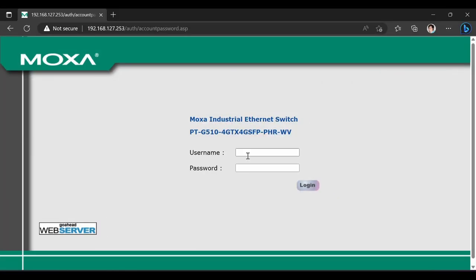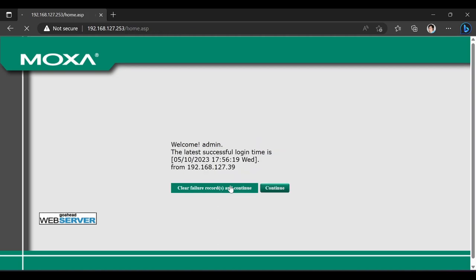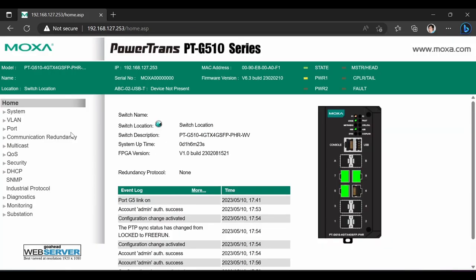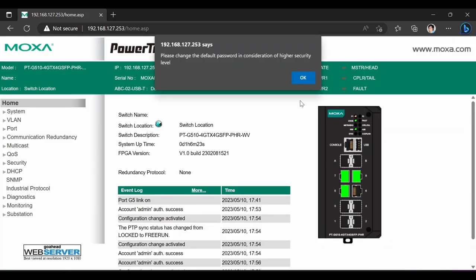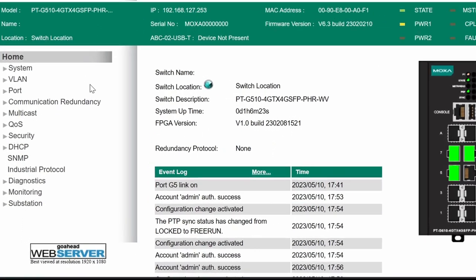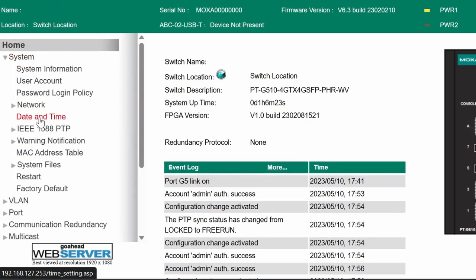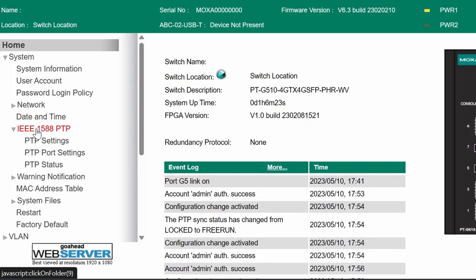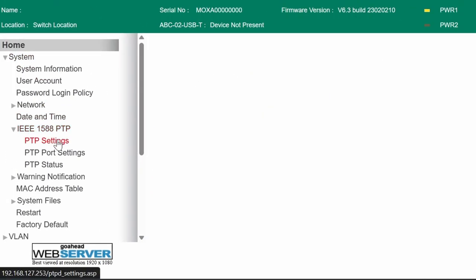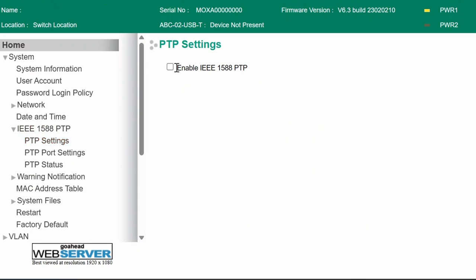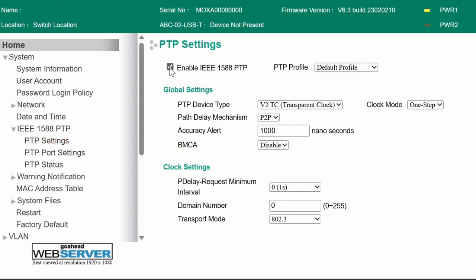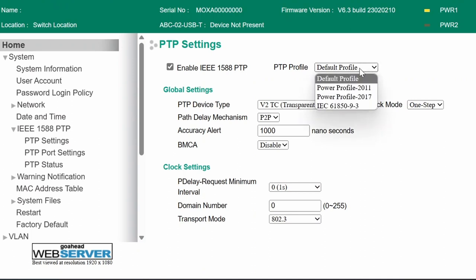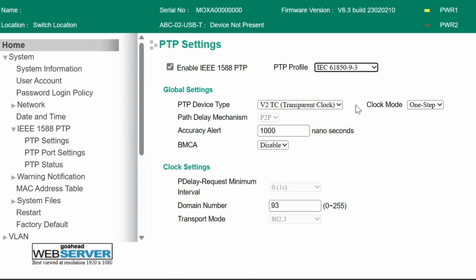Now let's log into the Moxa switch. I'll start with PT-G510 and navigate to system IEEE 1588 PTP PTP settings page. Here I need to enable PTP globally and select the same PTP profile that was configured on grandmaster clock.